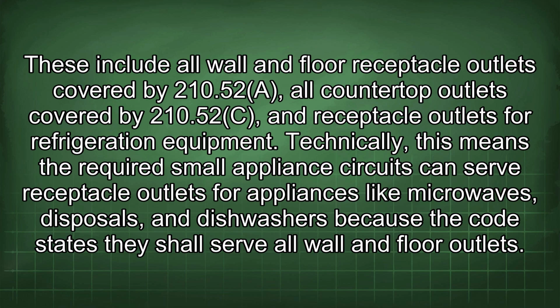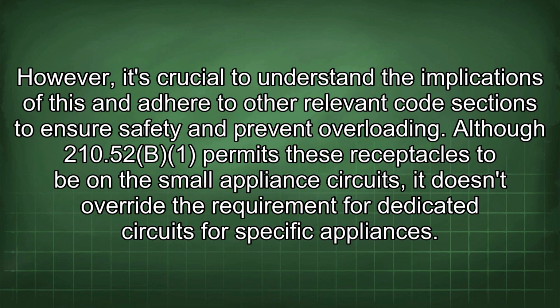Technically, this means the required small appliance circuits can serve receptacle outlets for appliances like microwaves, disposals, and dishwashers because the code states they shall serve all wall and floor outlets. However, it's crucial to understand the implications of this and adhere to other relevant code sections to ensure safety and prevent overloading. Although 210.52 permits these receptacles to be in the small appliance circuits, it doesn't override the requirement for dedicated circuits for specific appliances.